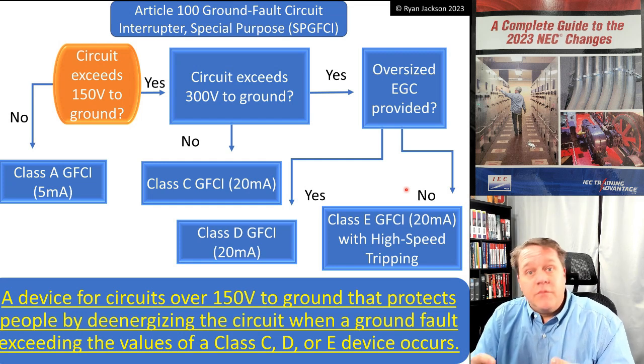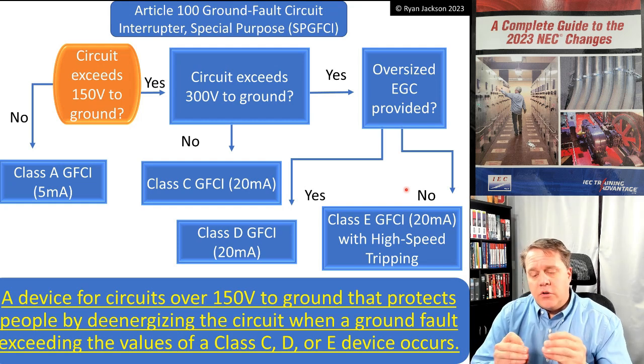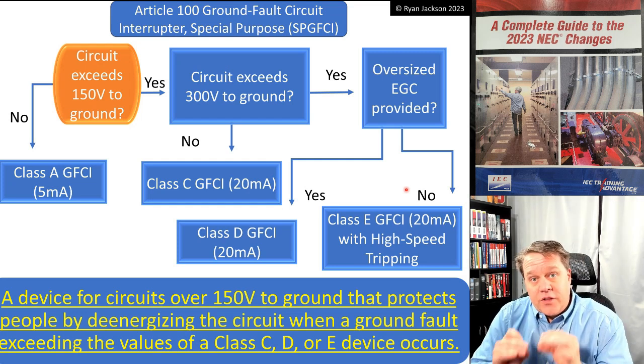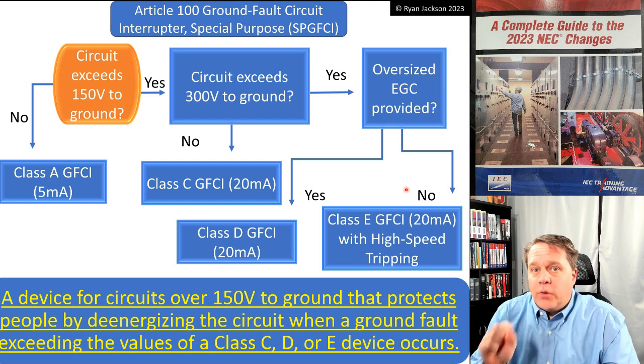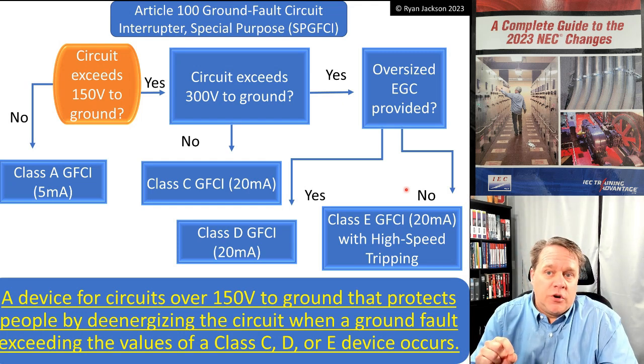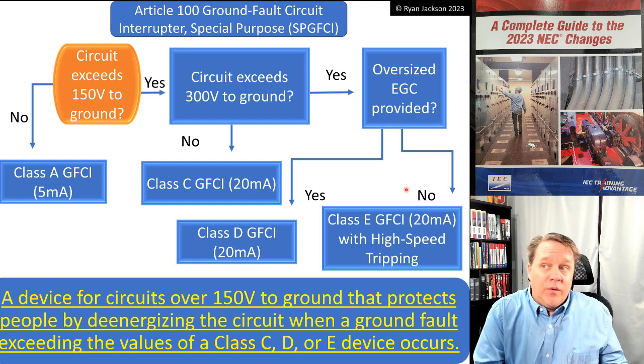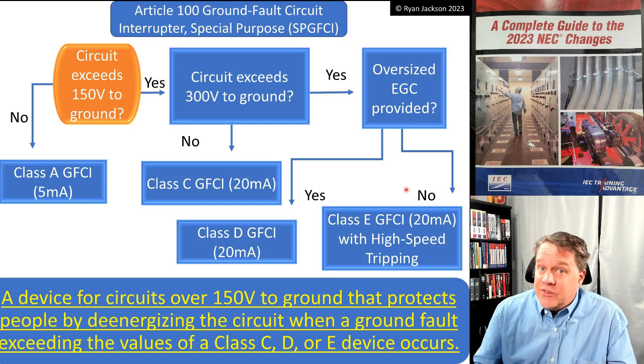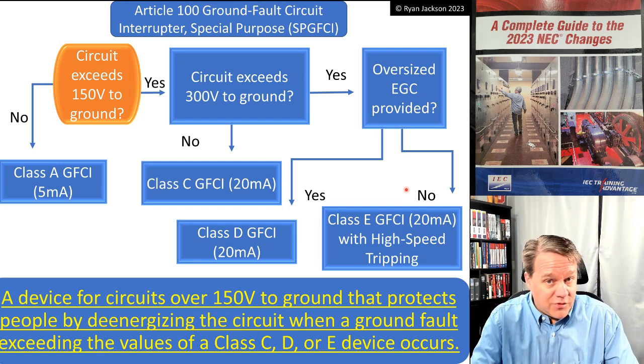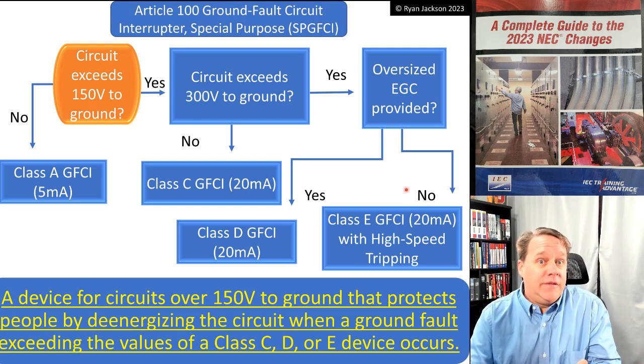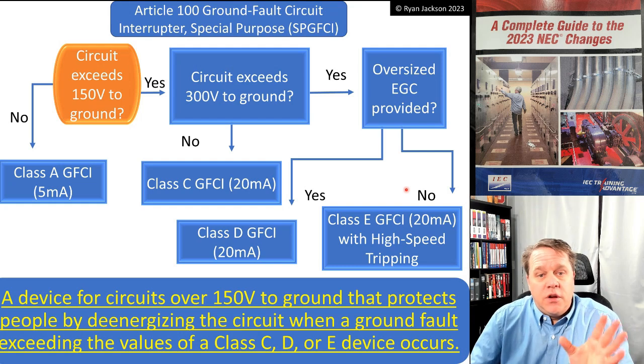Class C, D, and E don't trip if ground fault current is less than 20 milliamps — because with higher voltages comes higher leakage current. When you put 480 volts on a circuit, you stress the dielectric strength of the conductor insulation, and you will get six milliamps of leakage current whether you like it or not. You can't put a regular Class A GFCI on a 480-volt circuit because it will just trip — nuisance tripping. We want the swimming pool motor to actually turn on, but we also want the increased safety that a GFCI provides.